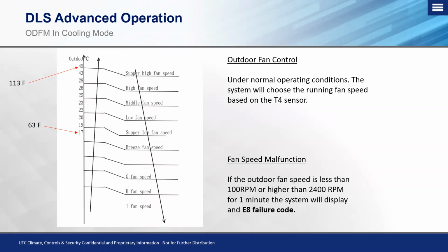So looking at the outdoor fan motor control in the ductless systems, you'll see on here, this is essentially a screenshot out of the service manual on different initiating conditions for different fan speeds. The outdoor fan control under normal operating conditions will choose the fan running speed based on that T4, the outdoor ambient temperature sensor. Now you can see on here at 63 degrees in the cooling mode, we're going to be running that fan at a very low speed. As we increase in outdoor temperature, we're going to increase in outdoor fan speed. And of course, that is all based off of that T4 sensor.